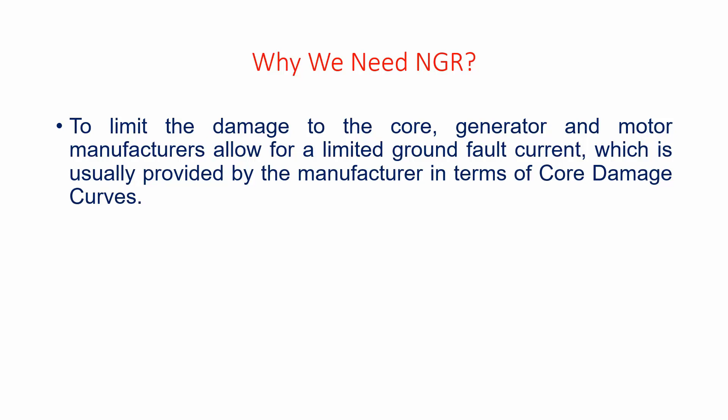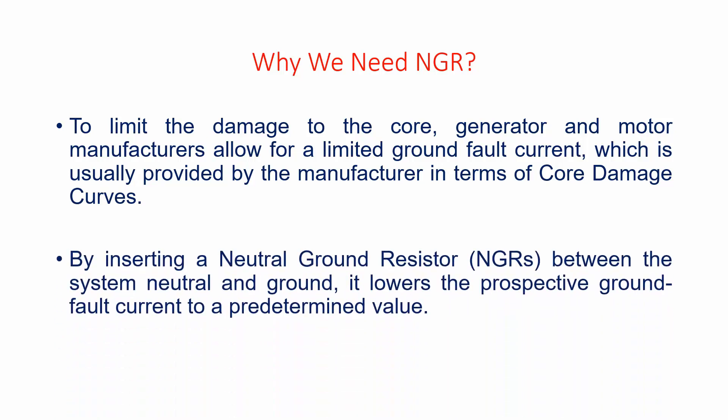The manufacturer will provide the amount of current allowed to the core of the generator and motor, so we have to restrict within this limit. That's why we need NGR. By inserting neutral grounding resistor, we can reduce single line to ground fault current to a predetermined value.